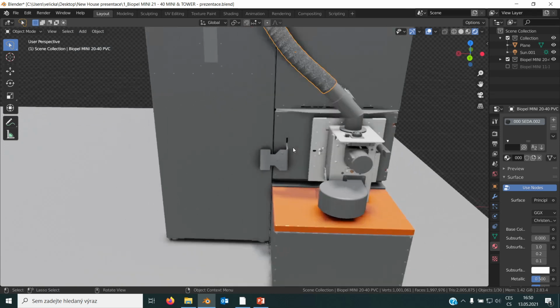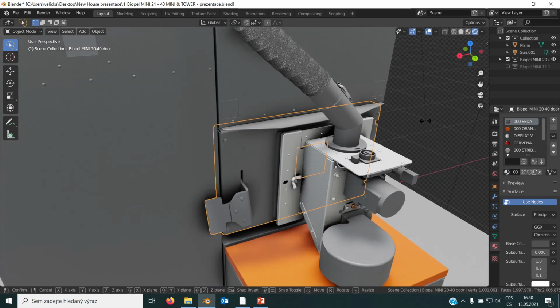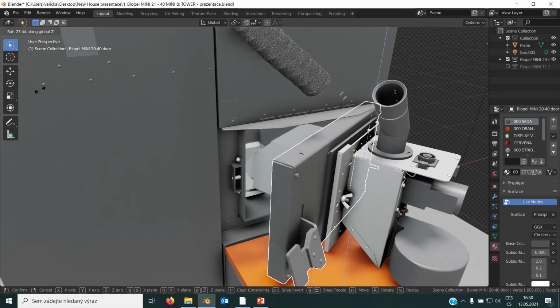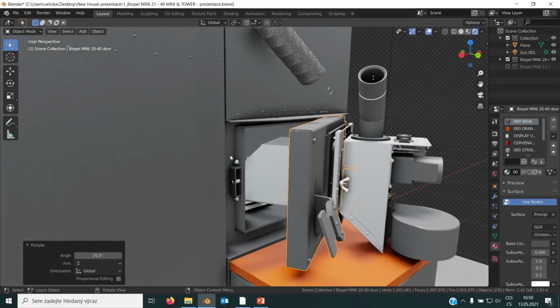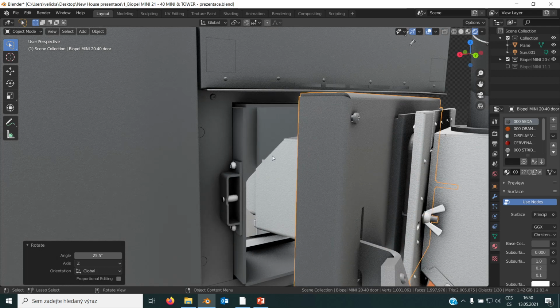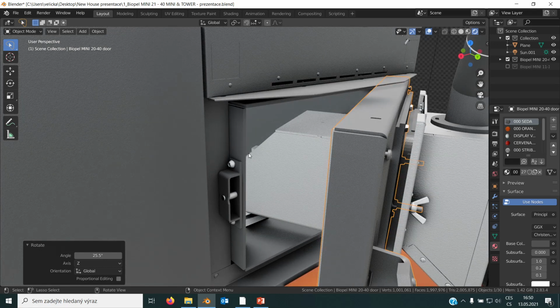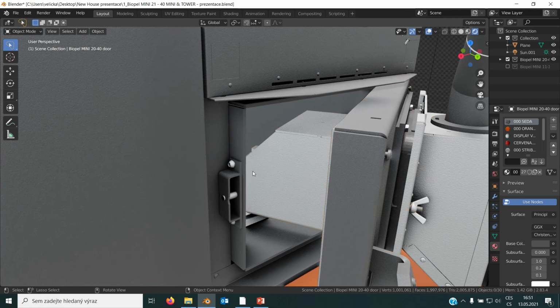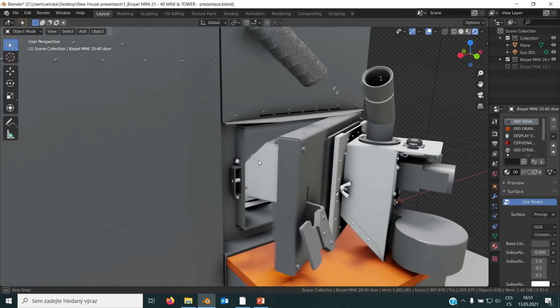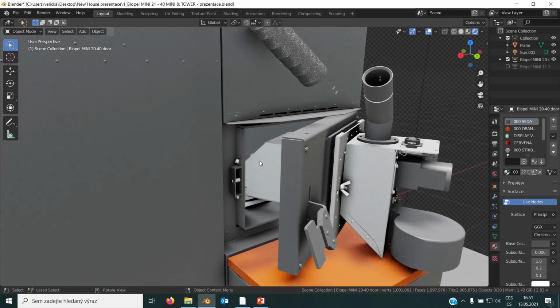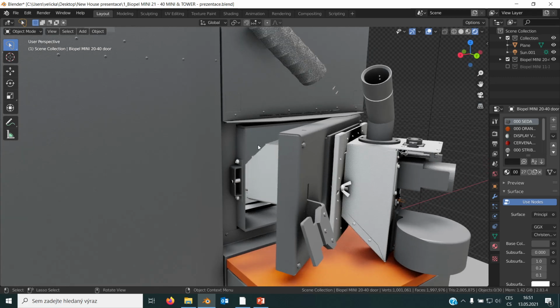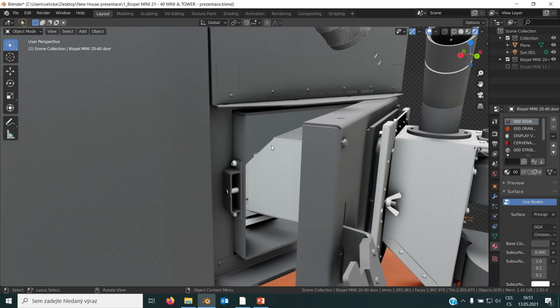And the second thing is that inside or behind the door, when you try to open it, you can open it something like that, okay, not more. Inside there is a metal plate, connected on the side of the door, which does not allow the burner to be opened fully. So you can open the door like this during combustion to see the flame. You can still check the flame, you can see the color of the flame, you can see the size of the flame. So manually you can adjust the combustion, but at the same time, because there is a protection plate, you cannot open the door fully.